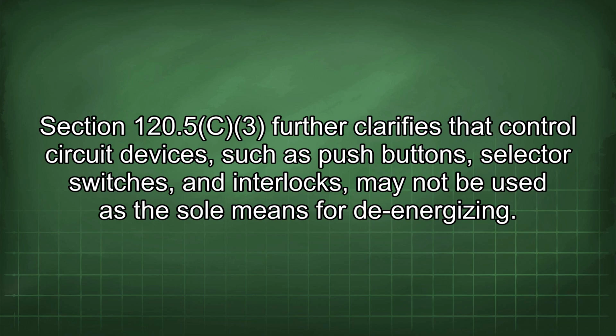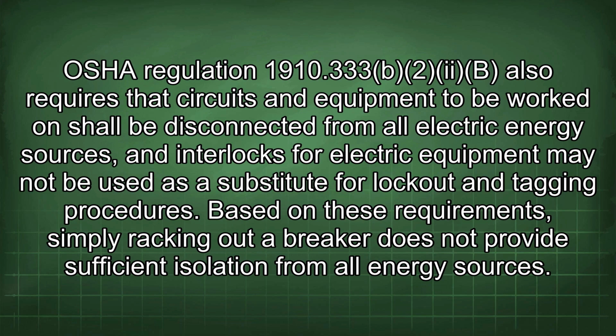Section 120.5c3 further clarifies that control circuit devices, such as push buttons, selector switches, and interlocks, may not be used as the sole means for de-energizing. OSHA Regulation 1910.333(b) also requires that circuits and equipment to be worked on shall be disconnected from all electric energy sources, and interlocks for electric equipment may not be used as a substitute for lockout and tagging procedures.